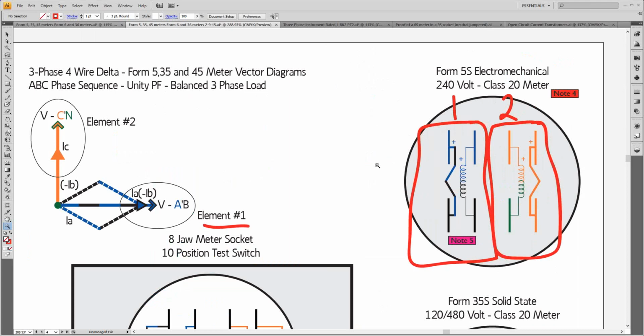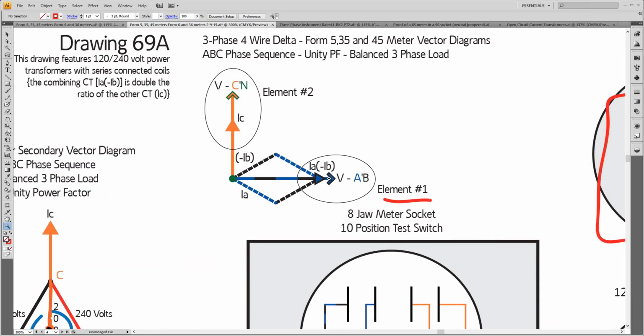And then, as far as the current that flows in the first element's current coil, again, if you own these books, the reason this is blue and black is because the summation of those two currents becomes a vector that I've drawn in as blue and black. And so if you see blue and black on a drawing, that's what I'm trying to show you: this is the summation current of what's happening between minus IB and IA, creating this current here that sits right in phase with A to B voltage. So the summation of those two balanced currents, again, you saw where it came from here, being reversed in that CT, puts it here. The summation becomes this magnitude here, which I said is 86%. But this current, I tap the screen with my little plus sign and zoom in.